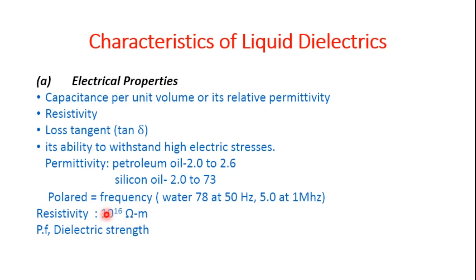Dielectric strength is the most important parameter in the choice of liquid dielectric for a specific application. It mainly depends on atomic and molecular properties of the liquid; however, under practical conditions it mainly depends on the material of the electrode, temperature, type of voltage applied, and gases contained in the liquid. These factors control the breakdown strength and lead to electrical breakdown of the liquid dielectric.